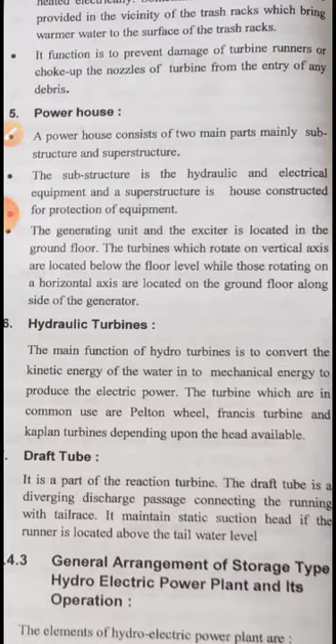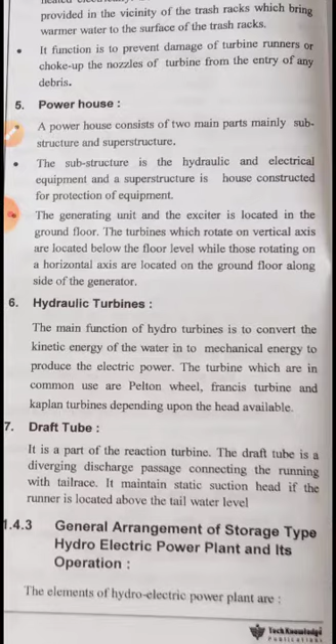Hydraulic turbines. The main function of hydro turbines is to convert the kinetic energy of the water into mechanical energy to produce electric power. The turbines in common use are the Pelton wheel, Francis turbine and Kaplan turbine, depending upon the head available. Draft tube. It is part of a reaction turbine. The draft tube is a diverging discharge passage connecting the runner with the tail race. It maintains static suction head if the runner is located above the tail water level.